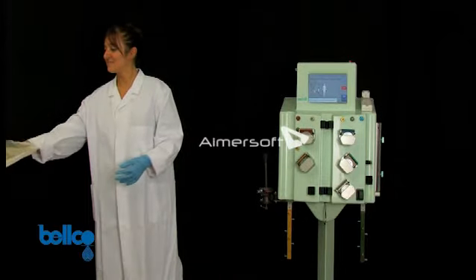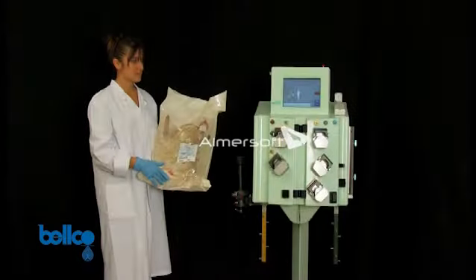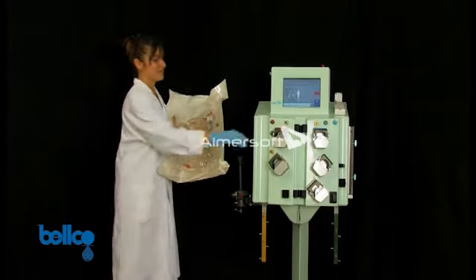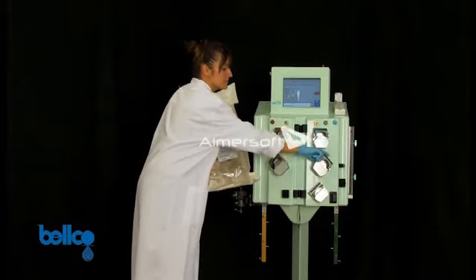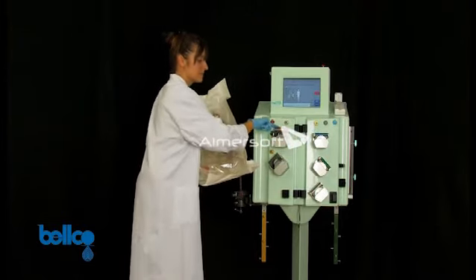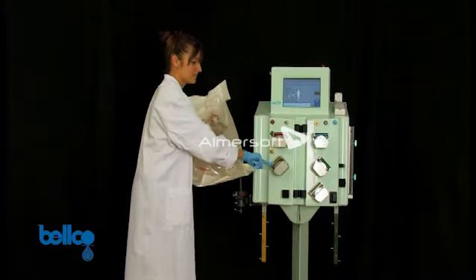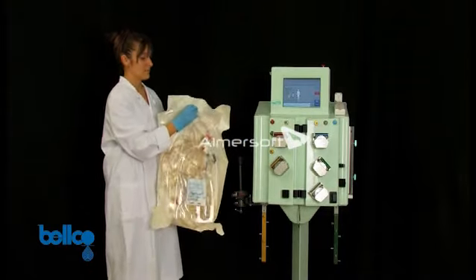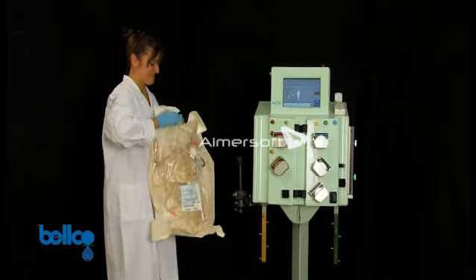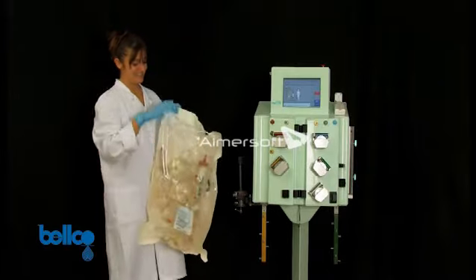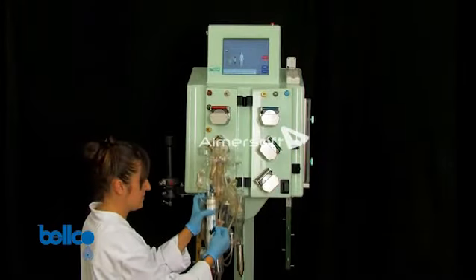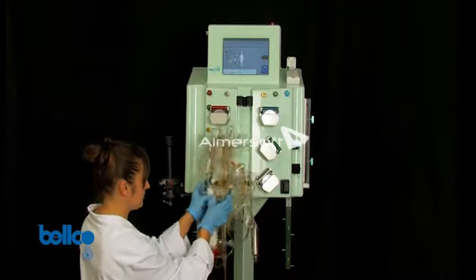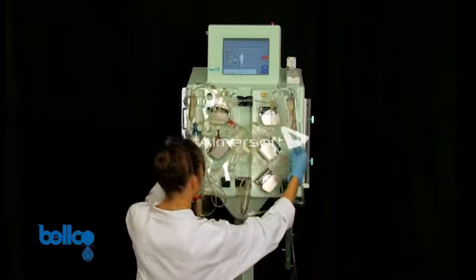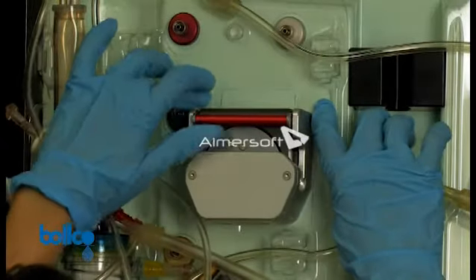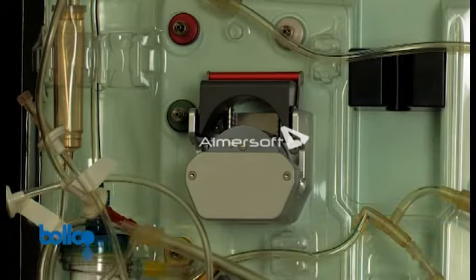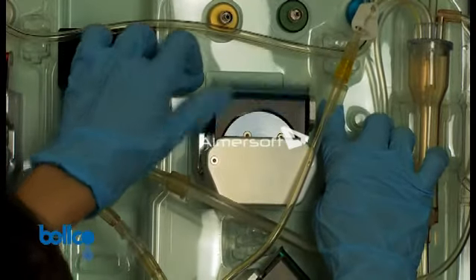Before installing the single-use device on the machine, check that all 5 pump covers are closed. Open the single-use device and position the set on the machine as shown. After positioning the set on the machine, fasten it by closing the pump covers. Fit the pump segments of each single pump.